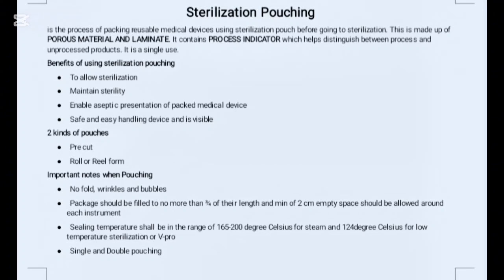There are important notes that we need to consider when pouching. There should be no folds, wrinkles, and bubbles because this might affect the integrity of the device. Package should be filled to no more than 3/4 of their length and minimum of 2 cm empty space should be allowed around each instrument.